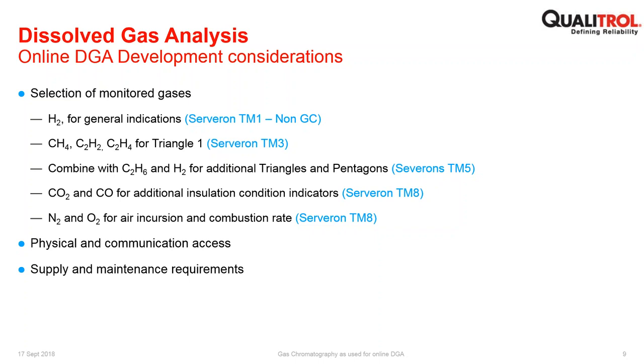Supply and maintenance requirements. So you've got to be able to maintain this product. In the case of gas chromatography, there are considerations in relation to calibration and carrier gases, for example, and you've got to have access to the monitor and a mechanism to manage those. You've got to consider the required accuracy, precision, and reliability. So it's not sufficient to achieve all of the above. You've got to do it with some specified accuracy and with some understandable level of reliability.